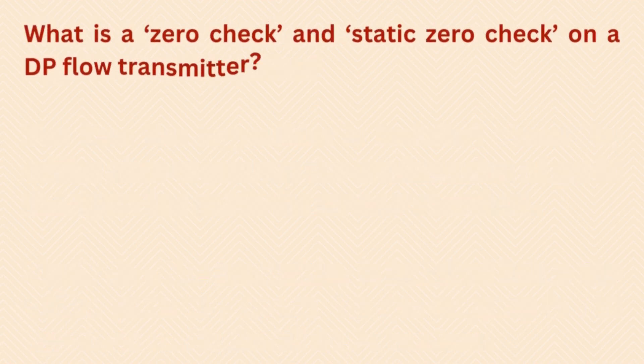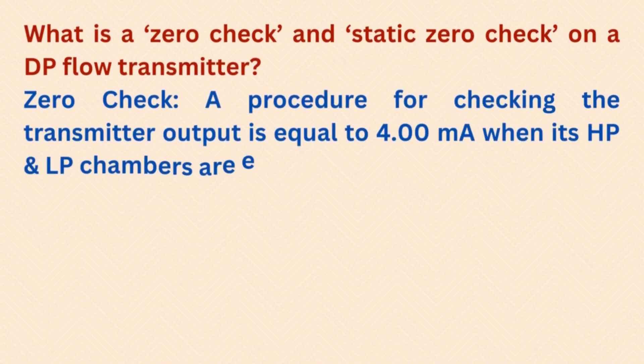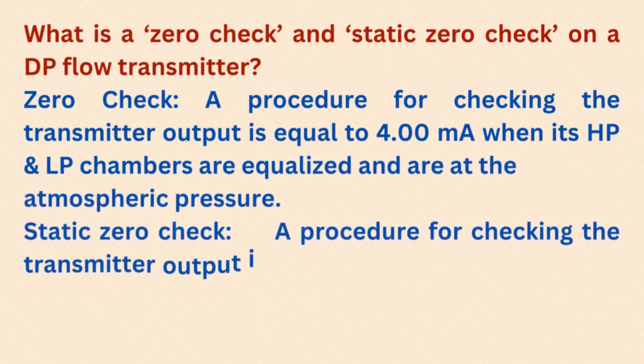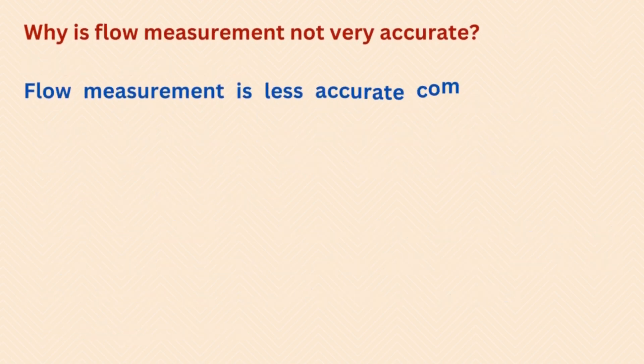What is a zero check and static zero check on a DP flow transmitter? Zero check is a procedure for checking that the transmitter output is equal to 4.00 milliampere when its HP and LP chambers are equalized and are at atmospheric pressure. Static zero check is a procedure for checking that the transmitter output is equal to 4.00 milliampere when its HP and LP chambers are equalized and are at operating pressure.